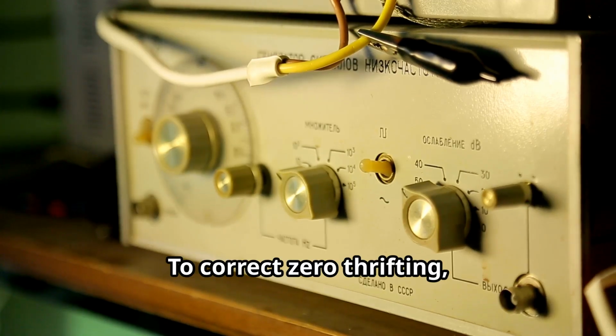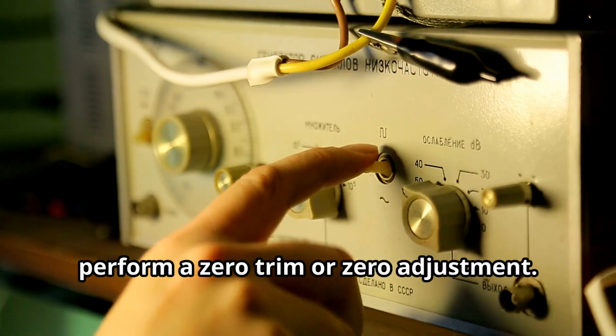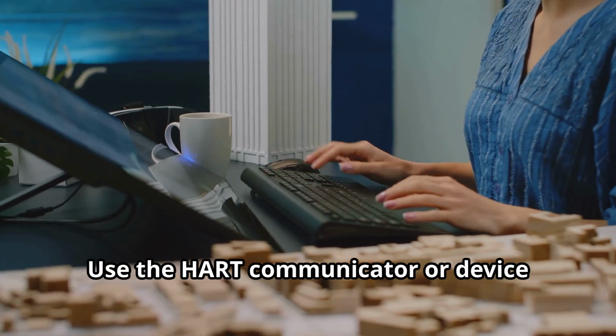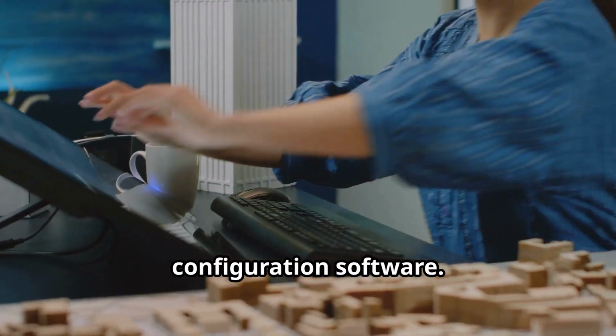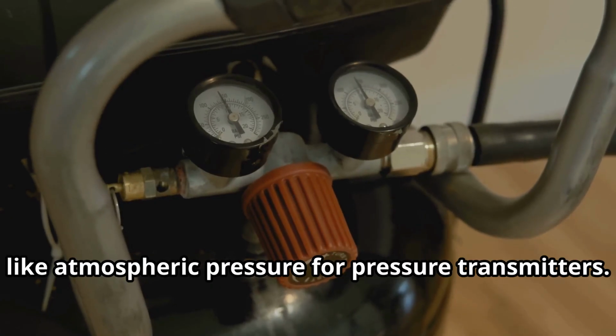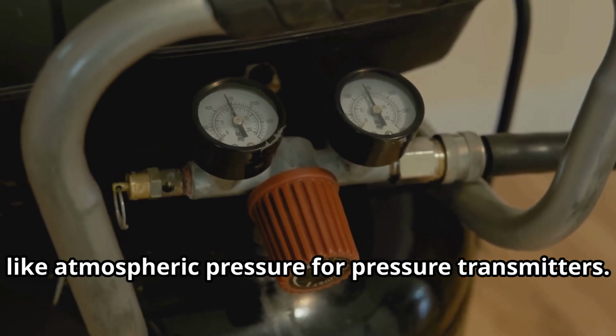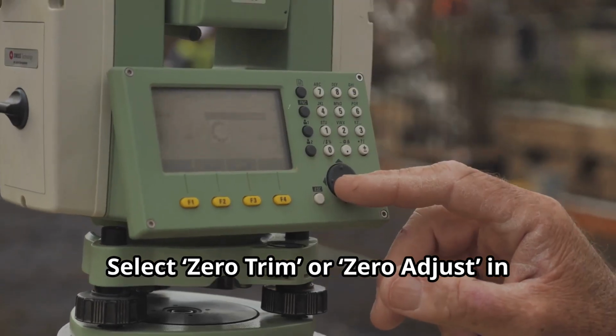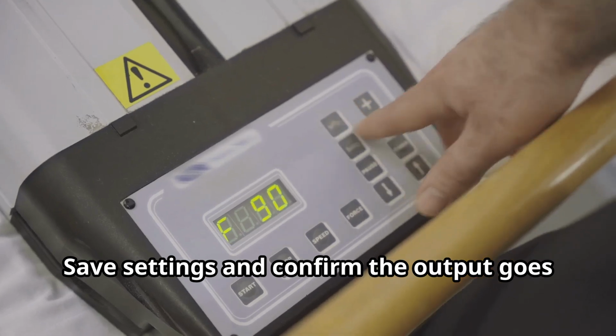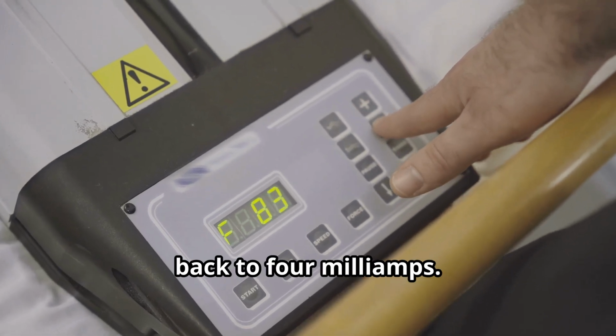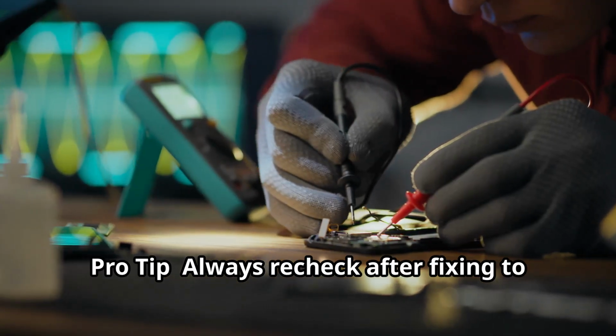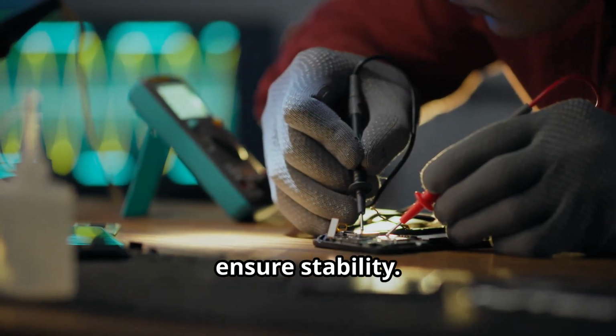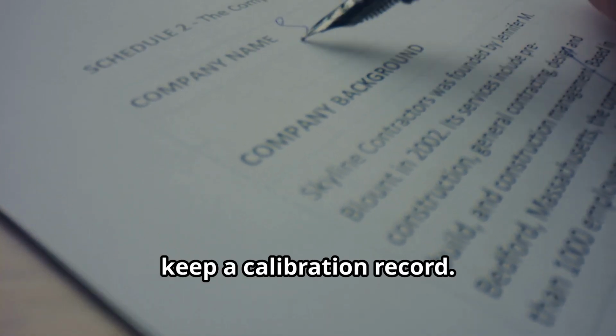To correct zero drifting, perform a zero trim or zero adjustment. Use the HART Communicator or device configuration software. Apply true zero input, like atmospheric pressure for pressure transmitters. Select zero trim or zero adjust in the menu. Save settings and confirm the output goes back to 4 milliamps. Pro tip: always recheck after fixing to ensure stability. Also, keep a calibration record.